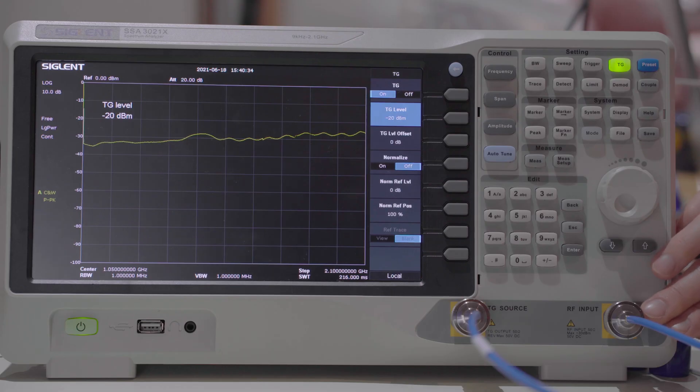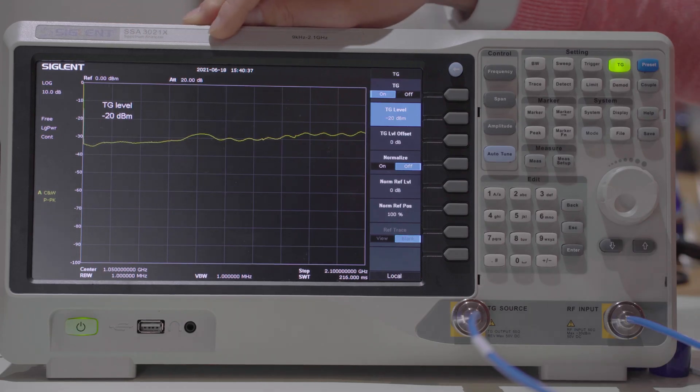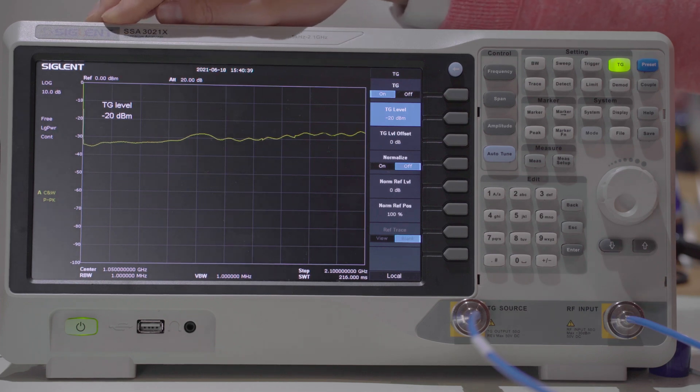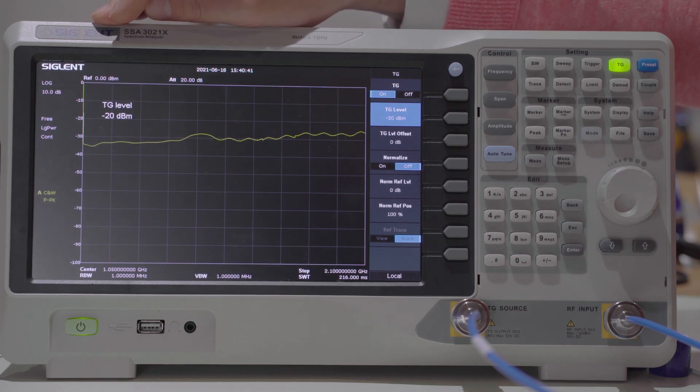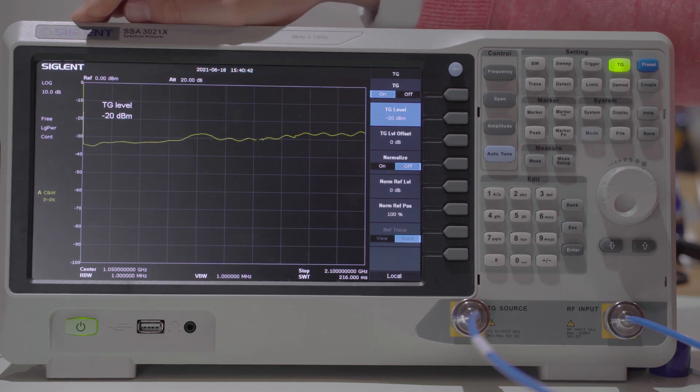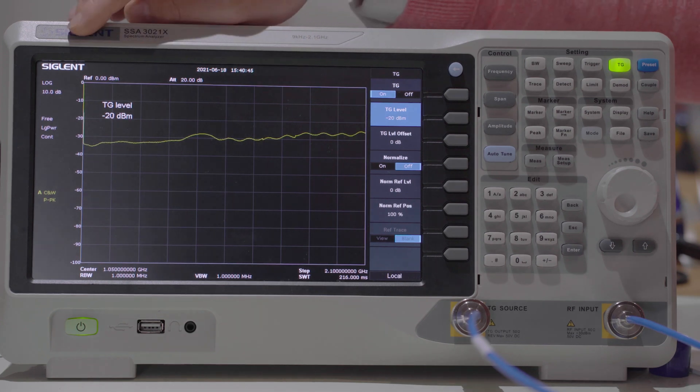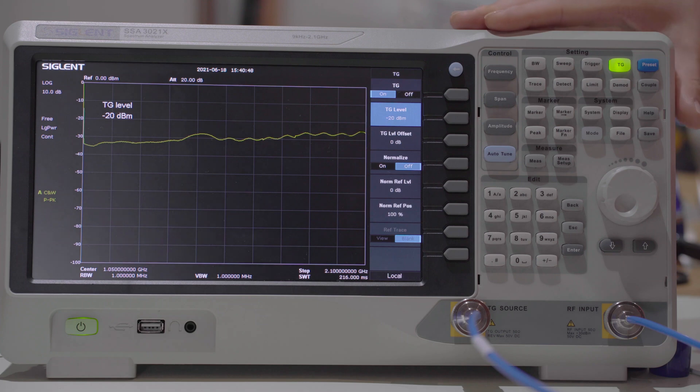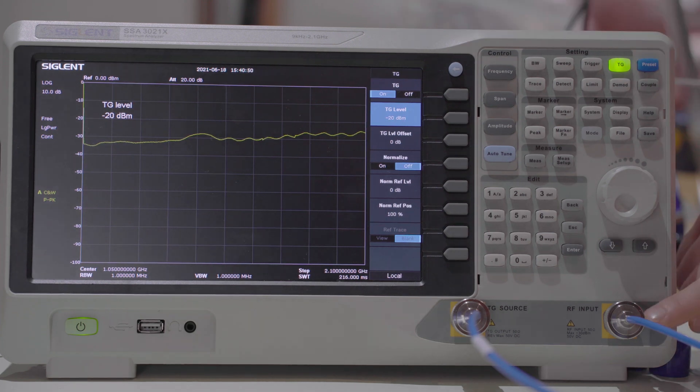And it can be seen very clearly if I set the spectral analyzer tracking generator on and I output minus 20 dBm output, and the receiving end of the front panel shows minus 35 dBm across the full range, so this is a clear sign of front panel damage.